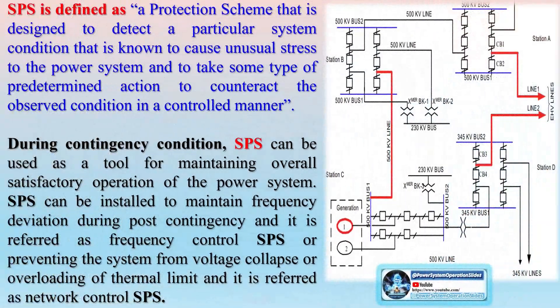In these schemes, depending on the type of problem, actions such as tripping of generators, intentional islanding of the system at predetermined locations, and tripping of loads will be taken. The design of SPS should be properly coordinated with the existing protection system to achieve maximum reliability. SPS are dynamic security control systems designed to control power system stability where the uncontrolled response is likely to be more damaging than the controlled response.